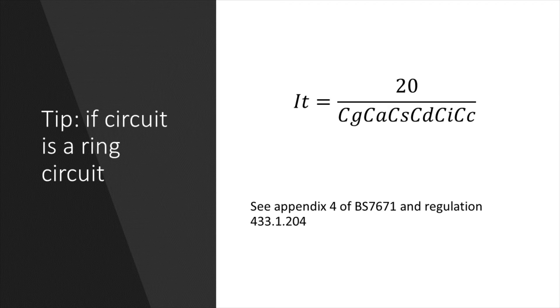Regulation 433.1.204 says that accessories to BS1363, in other words socket outlets, can be supplied by a ring circuit protected by 30 or 32-amp protective devices, the circuit having a minimum CSA of 2.5mm cable, except for mineral insulated cable. Such circuits are deemed to meet the requirements if the current carrying capacity IZ of the cable is not less than 20 amps. In other words, each leg of the ring circuit is not expected to exceed 20 amps.